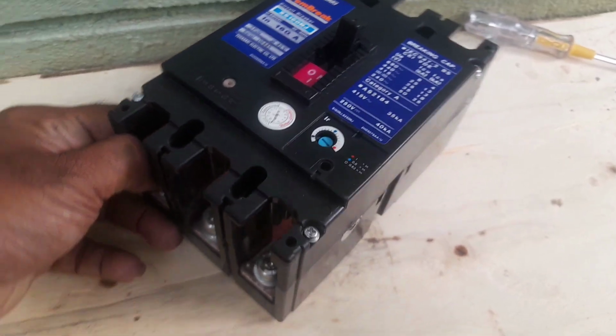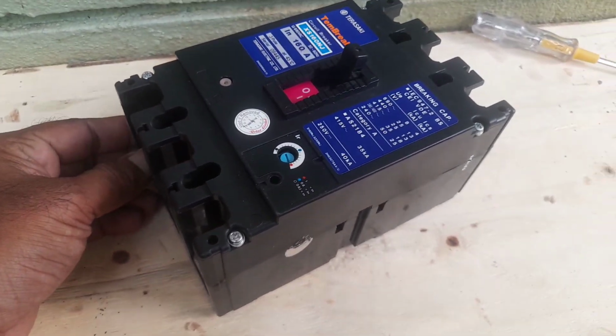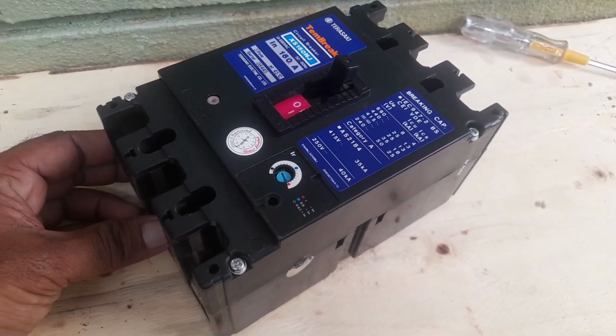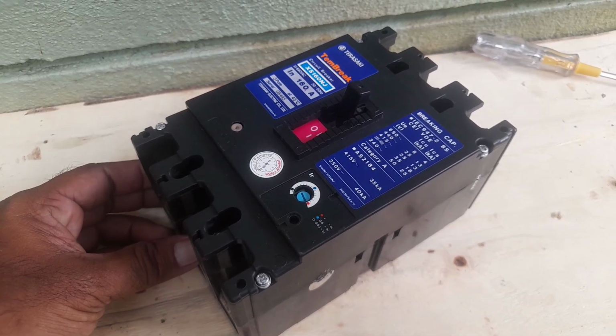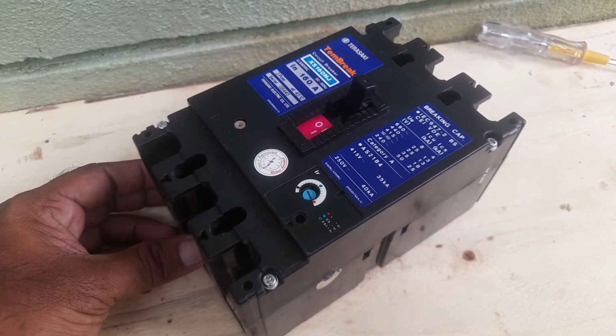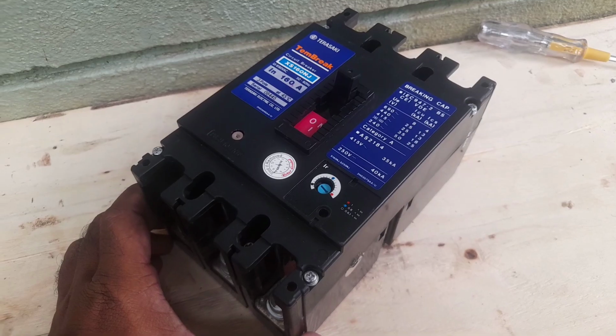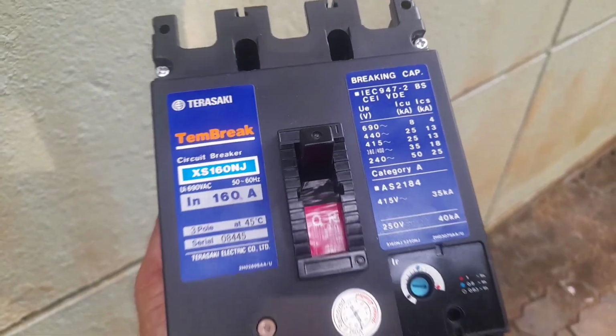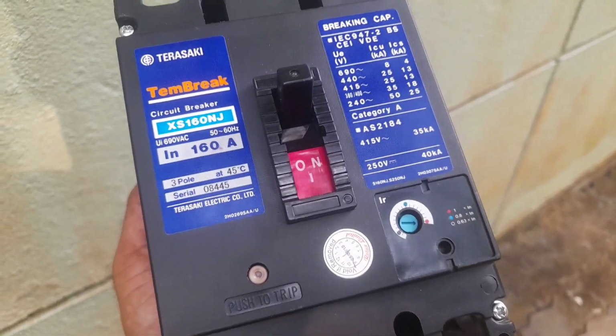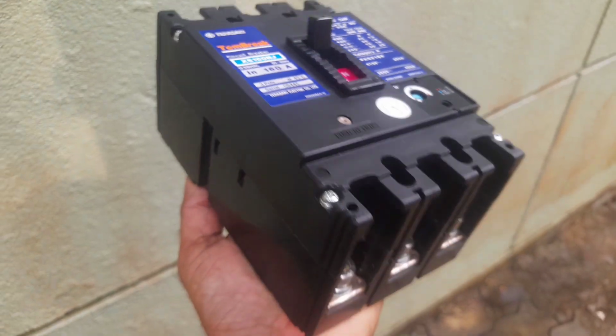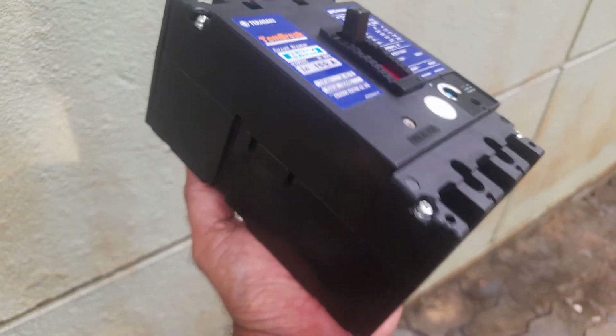The molded case or frame is the cushion that keeps all parts of the circuit breaker in place. It is solidly built from glass polyester or thermoset composite resin, which gives great non-conducting strength despite its compressed size. Terminals serve as connectors between external conductors and the molded case.